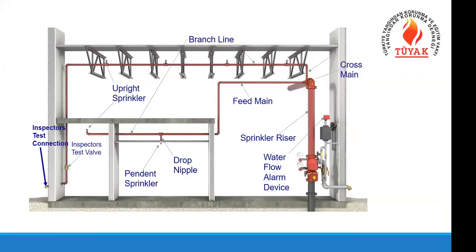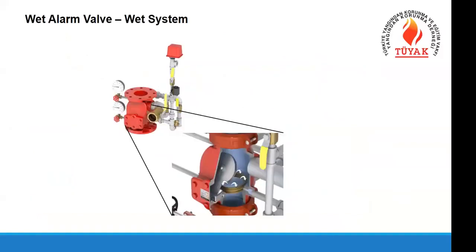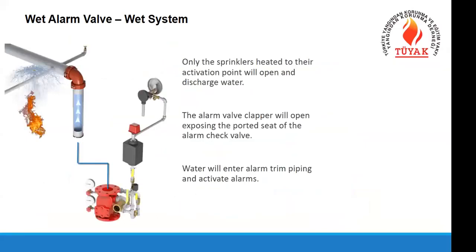This is a standard wet system. All the pipes are filled with water, and when the sprinkler operates, it discharges water immediately onto the fire. We use wet alarm valves here, which are called wet system alarm valves. These valves are typically a check valve that allows water flow in a single direction toward the sprinklers.